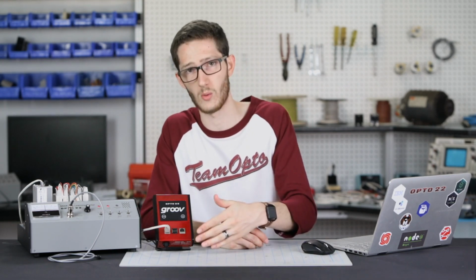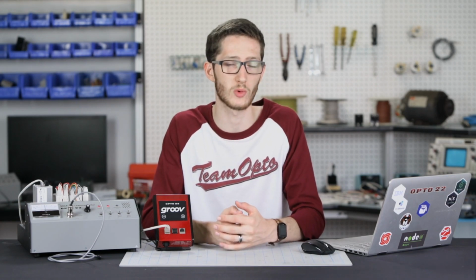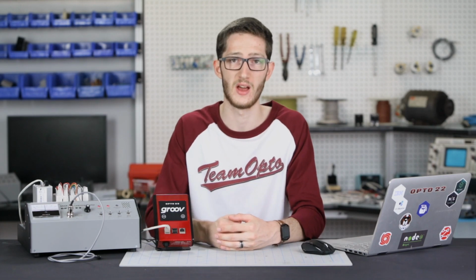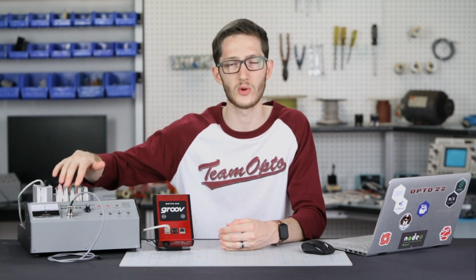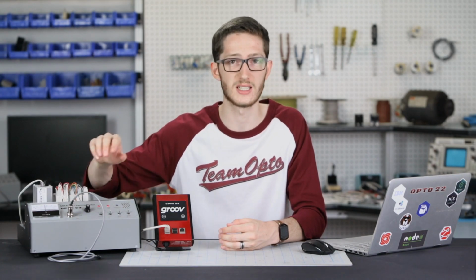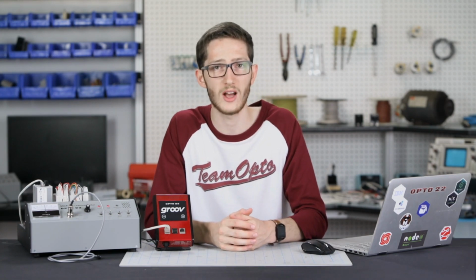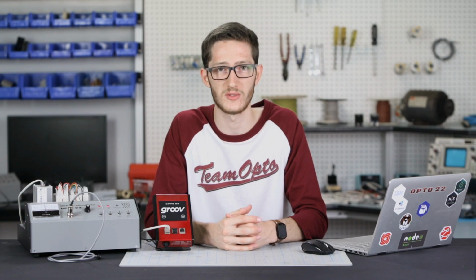This is a groov AR1 box. It's an industrially hardened IoT appliance that is running both groov and the Node-RED instance I'll use to move my data. I'm going to use the AR1 to bring these physical I/O points into Node-RED and regularly log the fuel level and temperature in a time series data table in a database named Workshops, running on a Microsoft SQL server up in the cloud on Amazon Web Services.